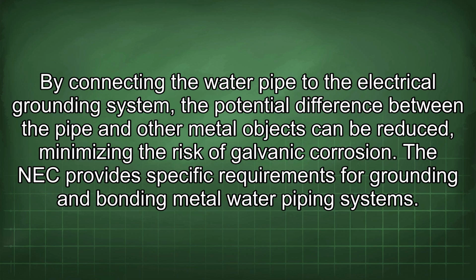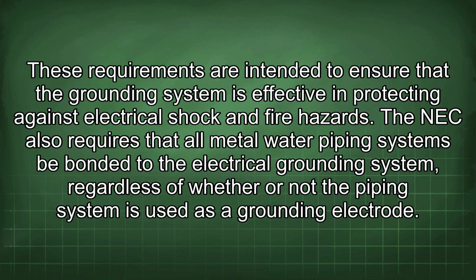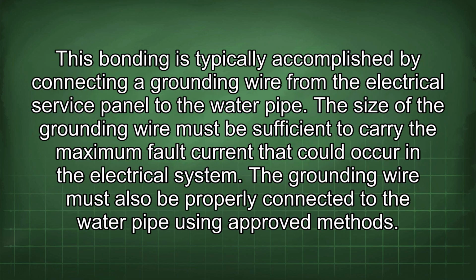The NEC provides specific requirements for grounding and bonding metal-water piping systems. These requirements are intended to ensure that the grounding system is effective in protecting against electrical shock and fire hazards. The NEC also requires that all metal-water piping systems be bonded to the electrical grounding system regardless of whether or not the piping system is used as a grounding electrode. This bonding is typically accomplished by connecting a grounding wire from the electrical service panel to the water pipe. The size of the grounding wire must be sufficient to carry the maximum fault current that could occur in the electrical system. The grounding wire must also be properly connected to the water pipe using approved methods.